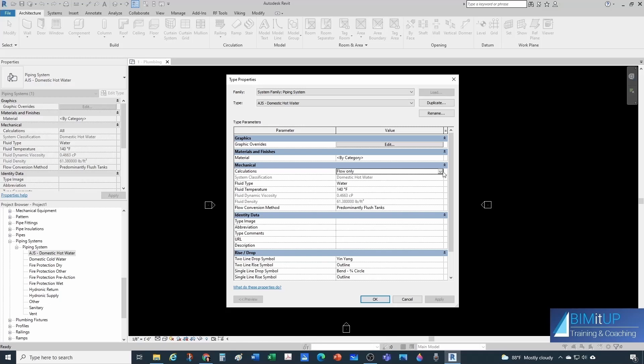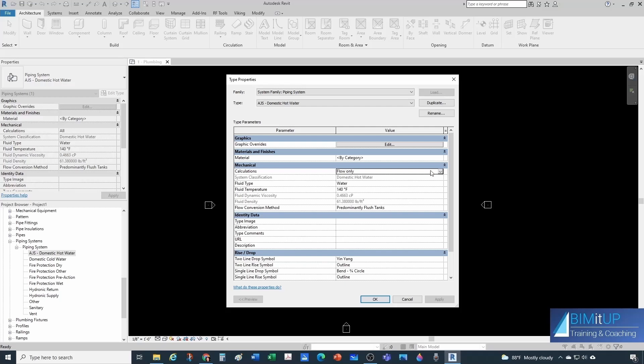If you just want to draw 3D pipes without Revit's smart calculation features, you can set calculations to None. But at minimum we'd like to have flow. Keep in mind that if you select All, you're calculating all flow parameters plus performance (pressure drops), which will slow down your system. Make sure you only pick what you're actually taking advantage of — in this case, let's keep it as Flow only.